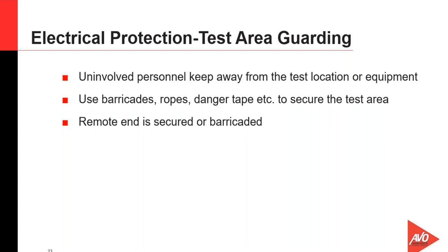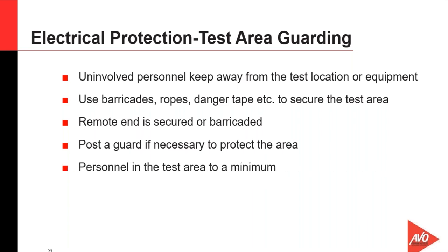The remote end of the cable needs to be secured. If we keep in mind that there are possibly two ends to this cable system, maybe even more, we need to make sure that we are securing and barricading those areas well, especially if we're going to be energizing that cable with a high current or a high voltage surge type voltage. Post a guard. If we have to, we can put a guard there and just let them guard the entire area and keep people away. And it may be that critical that we have to do that.